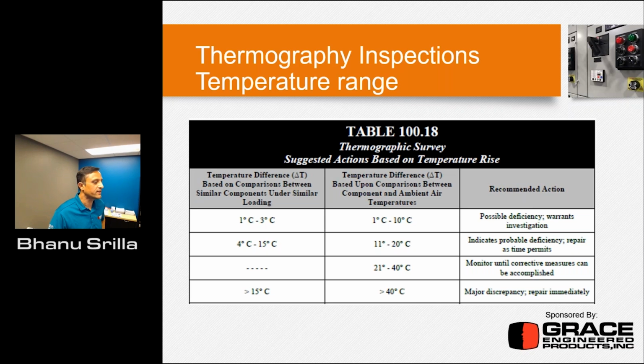So if there is anything in the 21 to 40 degrees C range, monitor until corrective measures can be accomplished, right? And then at 40 degrees, major discrepancy, repair immediately. So if you see something that's red hot or 40 degrees C, you just go and make sure that you perform this. The one more point I would like to add is, not just the 1 to 10 degrees here, it looks pretty normal, right? So possible deficiency warrants investigation.